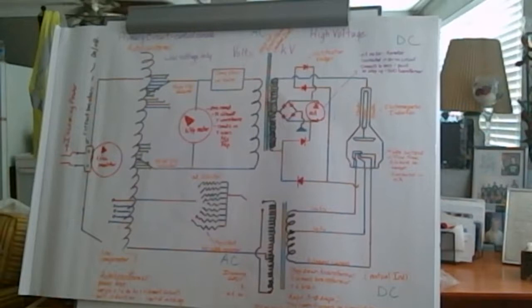That voltage variation is about 5%, a huge fluctuation that would make a big difference in our radiographs. One time your technique works and another time it doesn't. Who would want to work in a world like that? That wouldn't work well for us. So that's what the line compensator does.